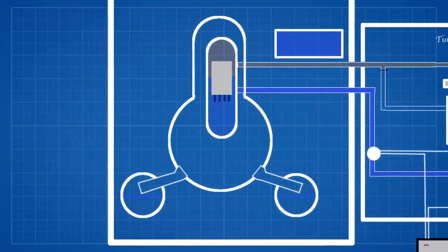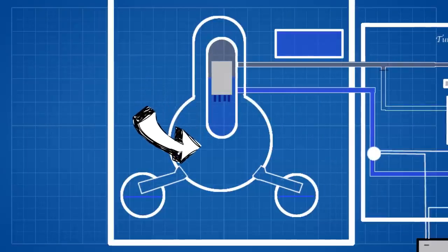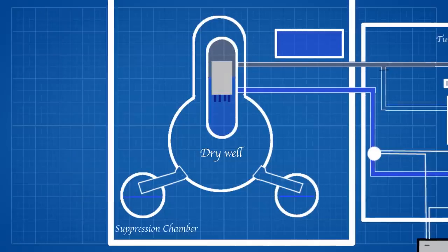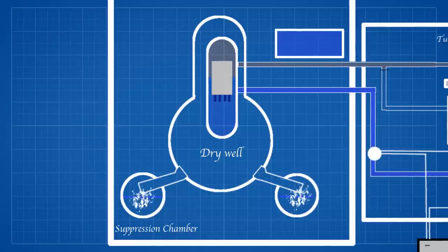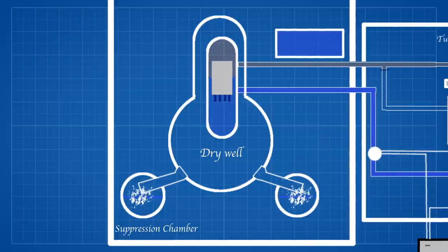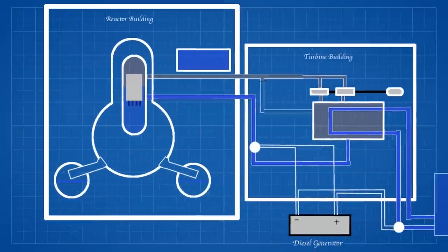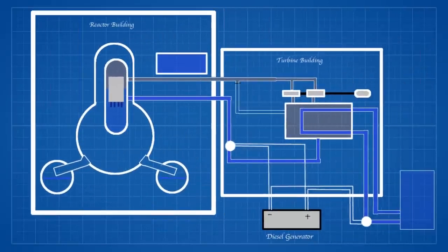The PCV has two major compartments. The reactor vessel is located in the dry well. The dry well is connected to a second compartment, the suppression chamber, which holds a large amount of water and enough space to suppress pressure increases. The water within the suppression chamber can be used to scrub radioisotopes from any gases released within the containment vessel. The primary containment vessels were filled with nitrogen to provide prompt control of any hydrogen generated during an incident. The secondary confinement is provided by the reactor building itself and is designed to try and hold any contaminant in a last line of defence of environmental protection.